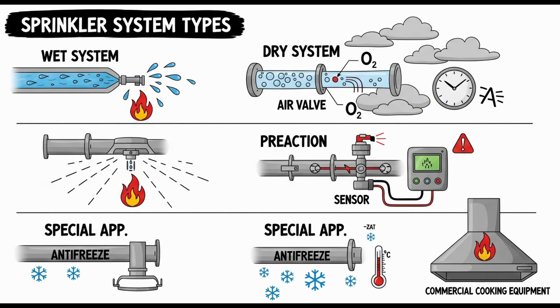However, for deep fat fryers specifically, the standard states that the sprinkler or automatic spray nozzle used to protect them must be listed specifically for that application. Its positioning, arrangement, location, and the water supply characteristics, pressure and flow, must be strictly in accordance with that specific listing. A special listing just for protecting deep fat fryers. Why the extra requirement there? Because fires involving large quantities of hot cooking oil or grease are unique and particularly hazardous. They have high fuel loads, potential for auto ignition, violent flare-ups, and the risk of splashing burning oil if water is applied improperly. Sprinklers or nozzles listed specifically for deep fat fryer protection have undergone rigorous testing to prove they can effectively control and suppress fires in this very challenging fuel type without causing dangerous splashing. Okay, specialized testing for a specialized hazard.